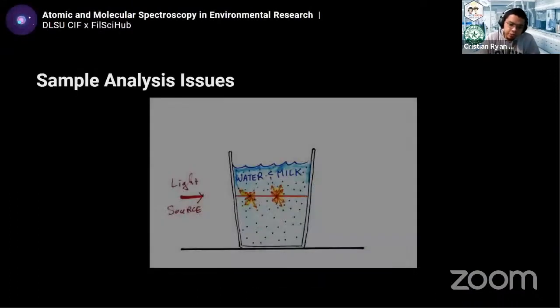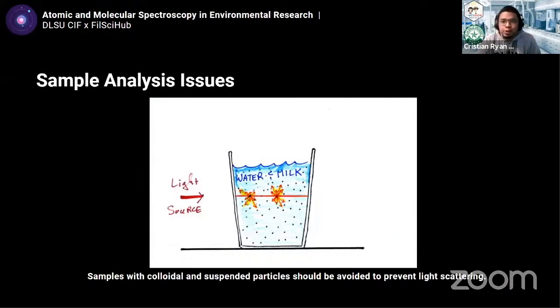Another very common issue that we often don't notice is when we prepare samples - I've already diluted it, dissolved the sample, it's okay, I'll put it in UV-Vis. It's important to know that when our samples have particulates, suspended particles, or colloidal particles, we have to ensure that these are minimized or eliminated at best. The concept we're using here is Lambert's, which says the path length is what the light passes through. In the case of a cuvette, it's typically one centimeter - the size or length of the cuvette. It's directly proportional to the absorbance of light. When that's the case and there are particles, the path of your light is disrupted, it's no longer straight. So whatever reading you get from the instrument won't be correct because the light that should pass straight through the sample was deflected.